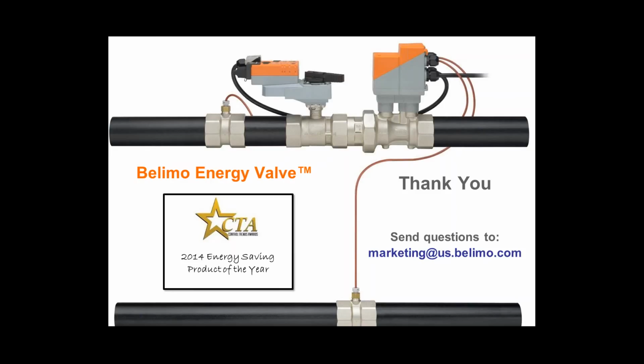So the BTU meter function has nothing to do with the delta T function. They're both separate and distinct. They're both beneficial, but they don't really interact. So the metering portion, again, if you're looking at the image on the screen in front of you, the valve portion itself on the left side with the actuator is a characterized ball valve, and then on the right side with the kind of square looking head on it is an ultrasonic flow meter, and then obviously we have the two temperature ports. So now we're able to measure the amount of BTUs being produced at that coil. Whether that's a value to you or not is totally another question, but that just kind of comes with the product because that's how it's built.